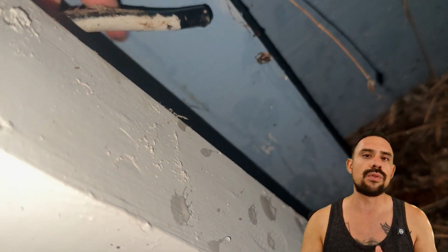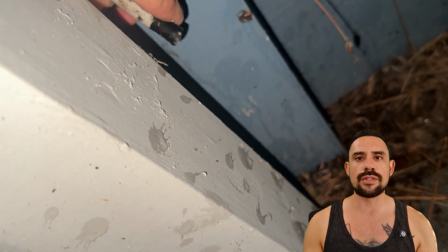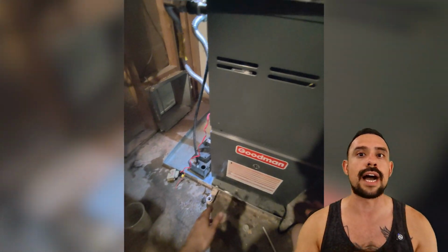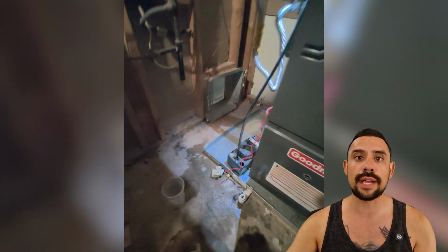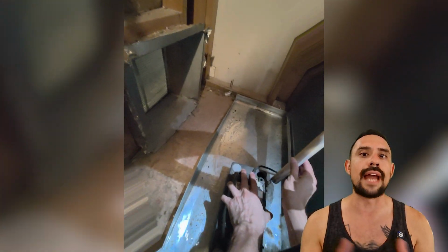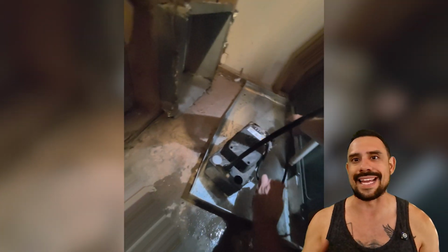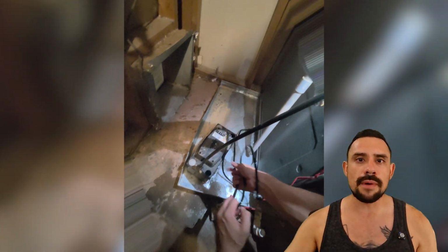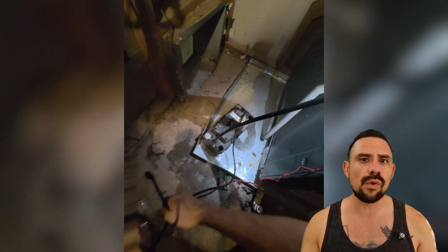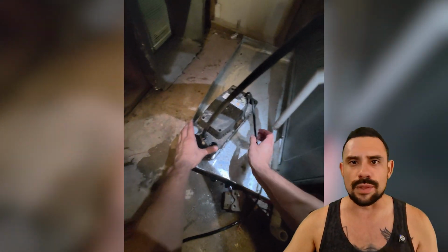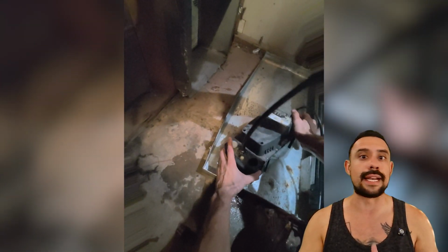To safely remove the pump, the first thing I am going to do is turn off the power to the entire HVAC system by flipping the main service switch. Then I'll unplug the pump's power cable from the outlet and pull it out from underneath the HVAC unit. From there, all I had to do was lift up the white PVC drain pipe to expose the pump by itself. When you lift the pump up, be careful because the reservoir is completely filled with water, and you don't want to spill it everywhere.